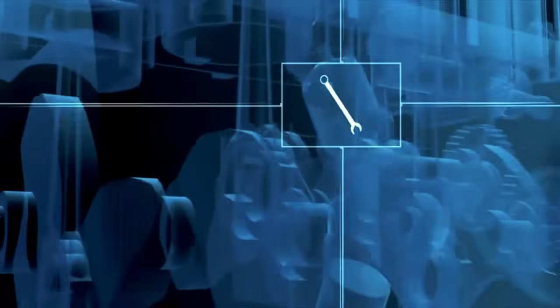Apparently, the boiler contractor lacked experience with local coal, having primarily worked with more reactive coals from Australia and Japan. This led to a mill design that could not grind the local coal finely enough. The coal delivered at Medupi had high ash content, high moisture, low calorific value, and inconsistent particle size. These characteristics exceeded what the units were designed to handle.